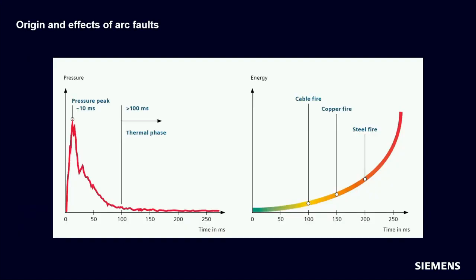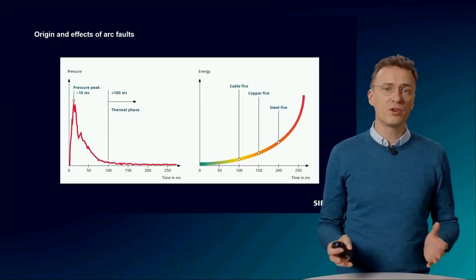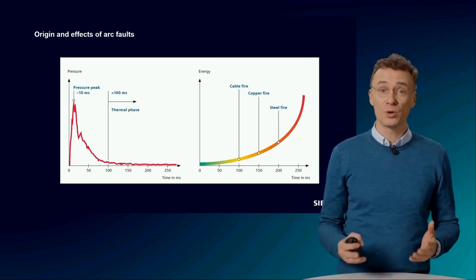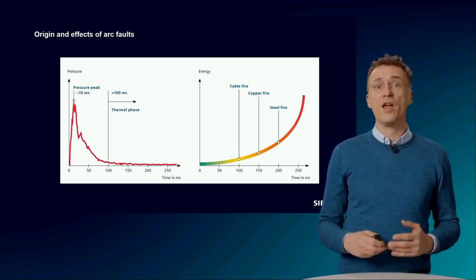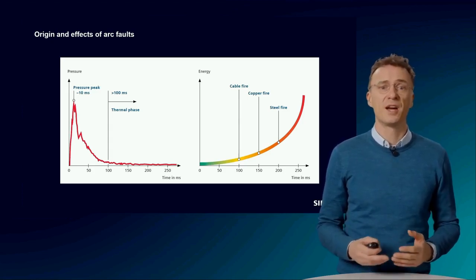The pressure rises rapidly, like an explosion — there's a bang. As a result, the temperature also rises sharply and can reach values of several thousand Kelvin. The high temperatures also burn or vaporize surrounding materials. The first thing that burns is the insulation materials of the cables, then the copper, and after some 200 milliseconds, the steel of the enclosure can also start to burn. The burning materials may also produce toxic fumes that should not be inhaled under any circumstances.